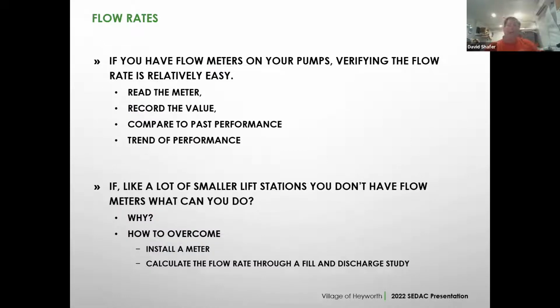The next piece that's good to look at is your flow rates. If you have flow meters on your pumps, verifying the flow rate is pretty easy—you read the meter, write the value down. Every 4 to 6 months, you go back and look at it and say, hey, pump two's slowing down, our flow rate's not doing so good as it was a year ago. I wonder what happened. Let's pull that pump and take a look at it.